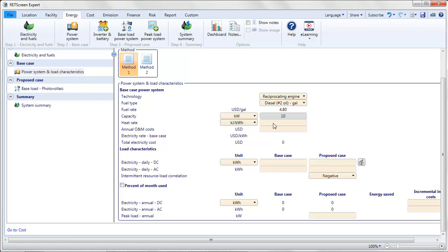There are at least two ways to get this. One is to find the fuel consumption of the generator, say in gallons per hour, convert that into gallons per kilowatt hour, and then convert the gallons of fuel into kilojoules of energy contained in that fuel. That would be a way to get to the heat rate.